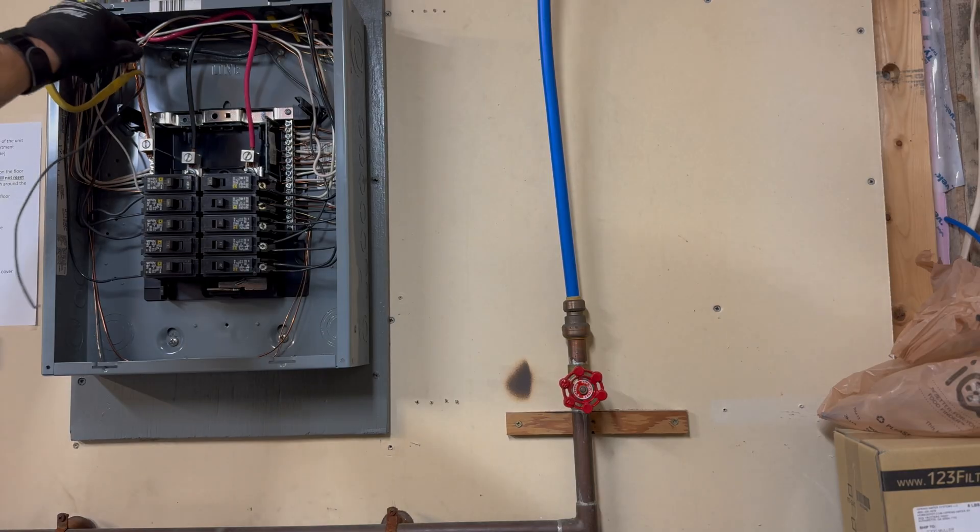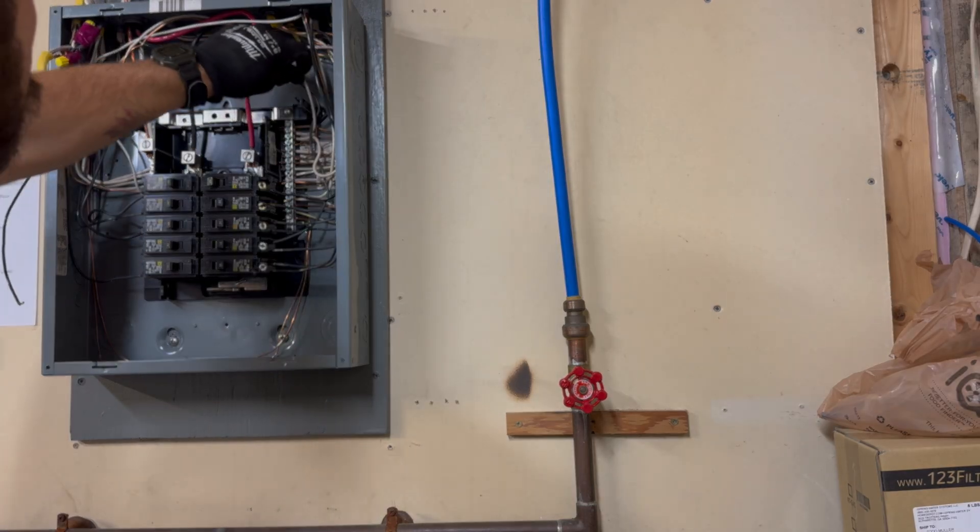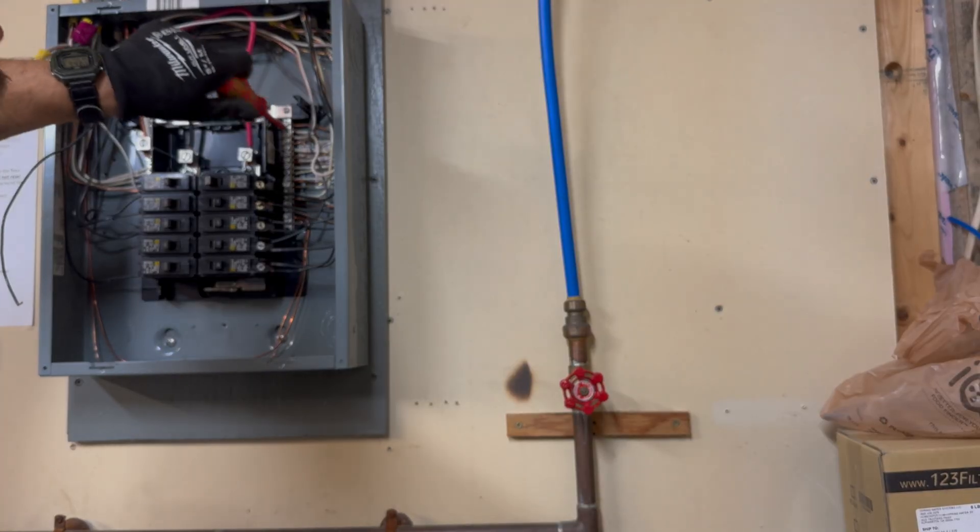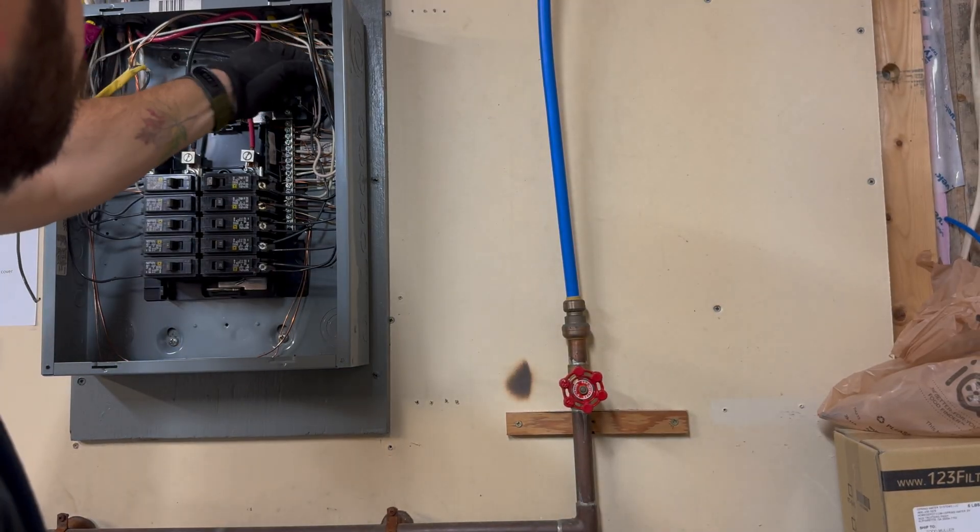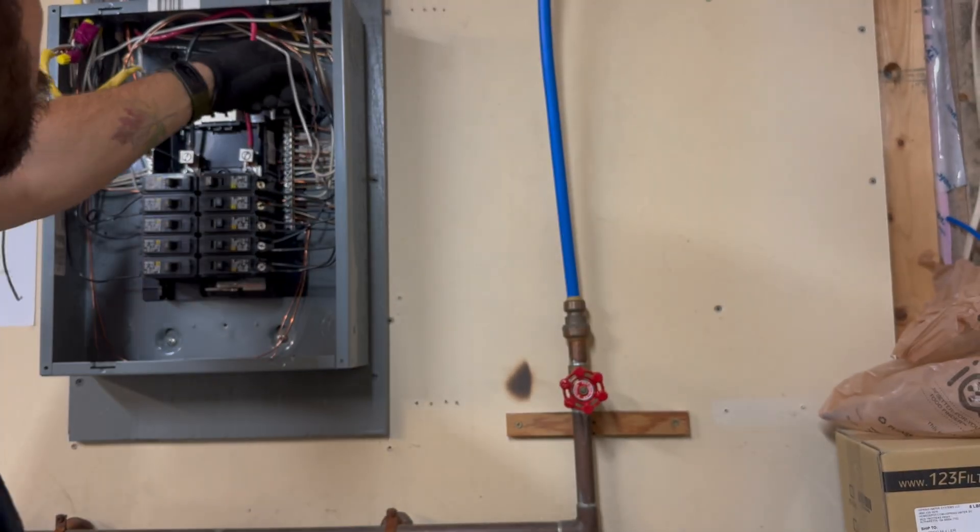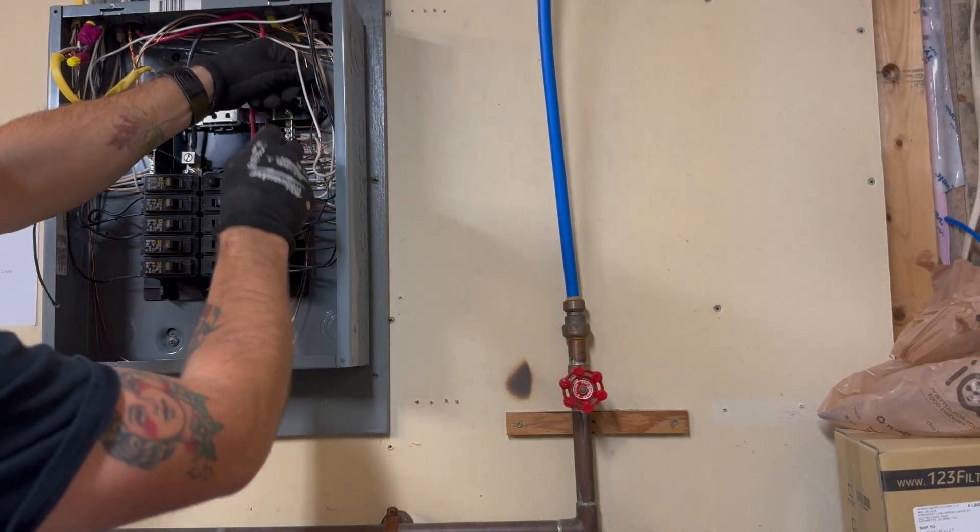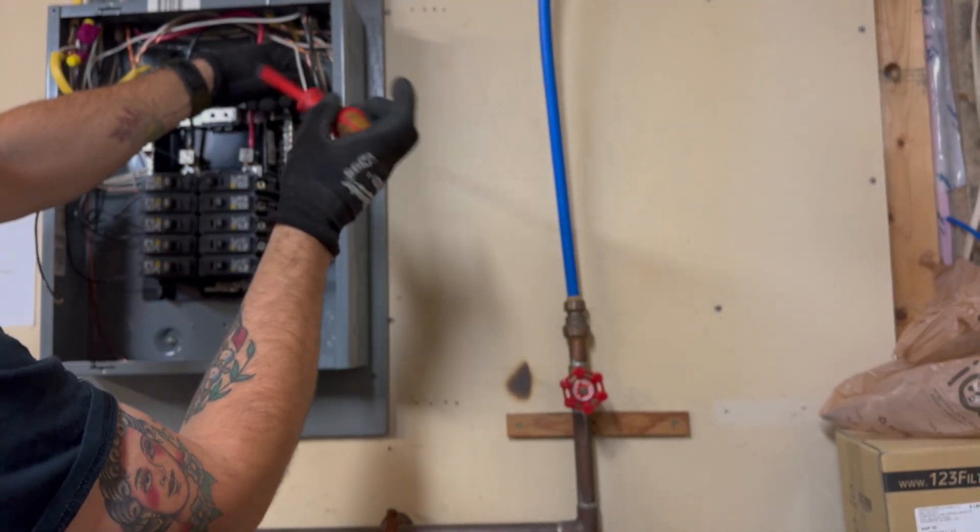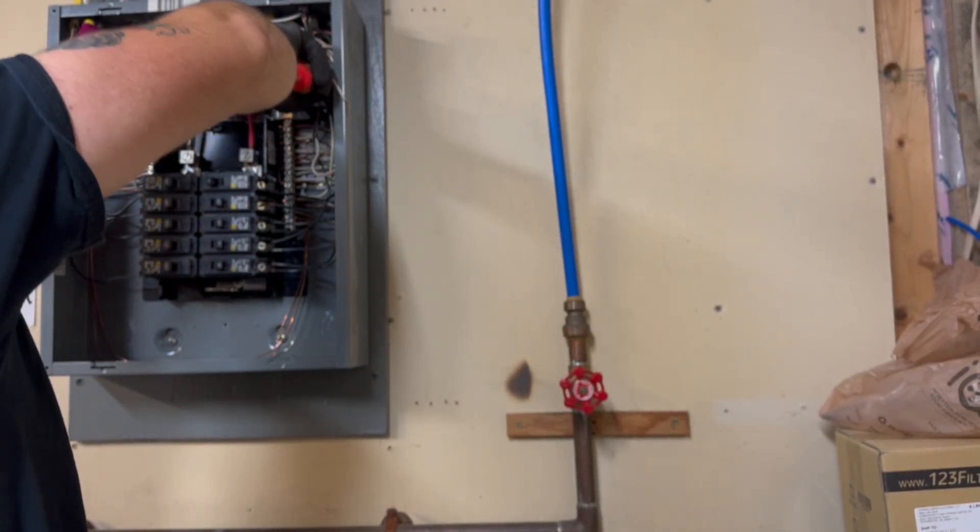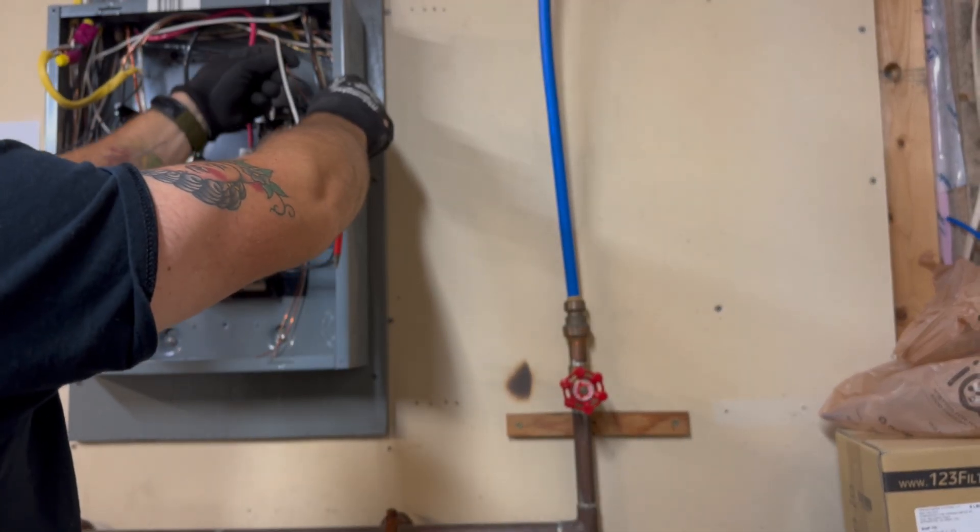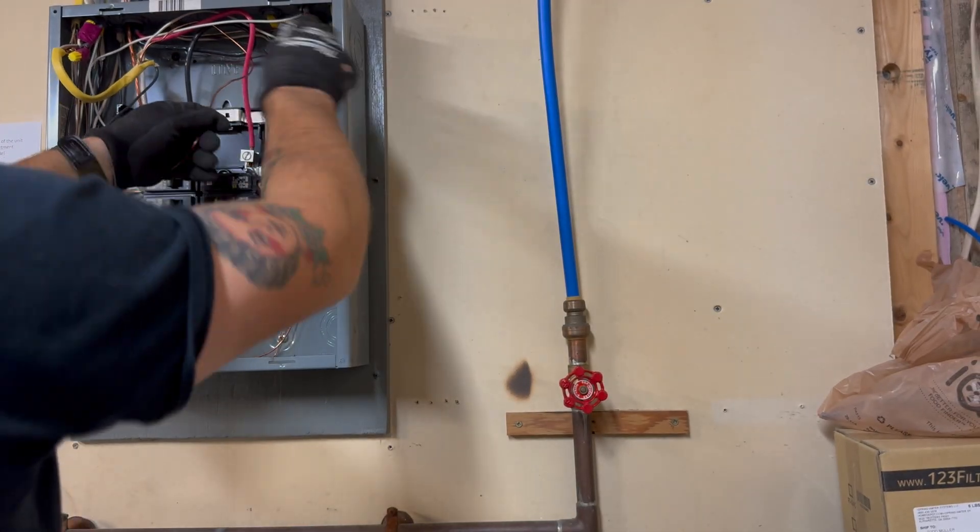First thing I did was redo this splice here. There was a splice made up in the panel. Clearly some UF was not long enough and they had to make a pretty goofy short splice with some strange purple tape. So I disassembled that whole circuit and reworked that, which you'll see in the final.